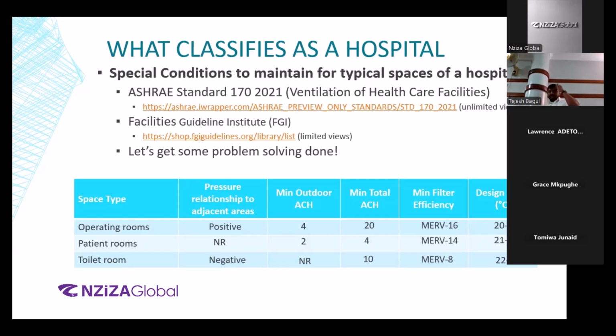Now, the next column is regarding the minimum total air changes per hour. Okay. So this is just outdoor air we are talking about. The air that we are bringing from outdoor to the indoor to make sure that the indoor air quality is maintained. Yes. So how can you measure the air changes per hour? The question was, for the online folks, how can we measure the minimum air changes per hour? So first of all, we'll need to have the formula for it, which will give us a CFM. And based on that CFM, we will have airflow measuring stations that will measure how much CFM is being moved in a given particular room. Does that make sense? Okay.